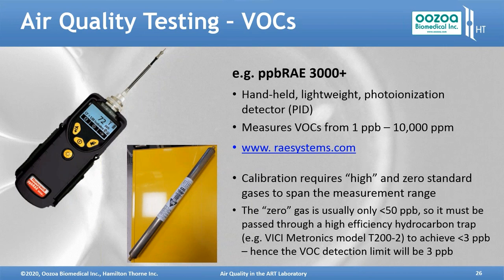So we pass the zero calibration gas through a high efficiency hydrocarbon trap. And that hydrocarbon trap, this one shown here, is about 2'6" long, so about 70, 75 centimeters long. It's big. It has standard quarter inch Swagelok fittings on the end, so we can connect the piping to it, and that's the direction of flow, so the gas is connected to this end, and this end goes to the sampling device of the ppbRAE 3000.